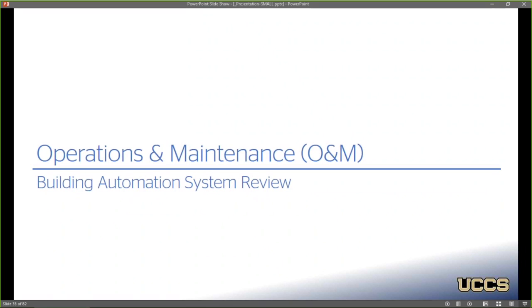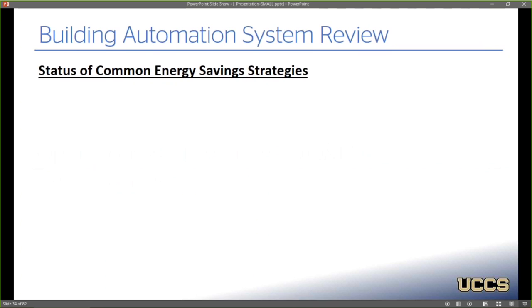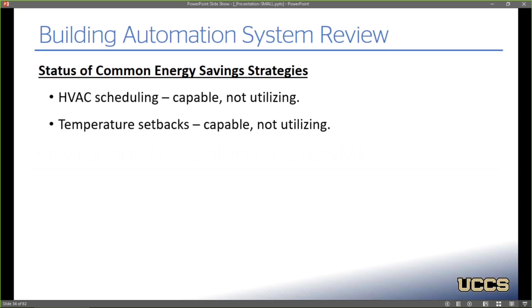So looking at the building automation system, this was kind of the crux of a lot of this audit, in trying to figure out how we get these systems to not run 24/7. So first I looked through the logic and tried to identify any energy savings strategies that I would expect in a building like this. So HVAC scheduling, the system is definitely capable of doing that, but it's not actually utilizing it. Same thing with temperature setbacks, capable but not being used.